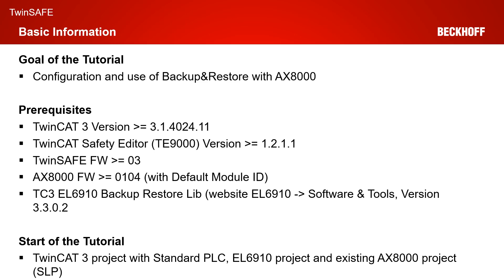As prerequisites, we need a TwinCAT 3 version greater or equal to 4024.11, a TE9000 version greater or equal to 1211. We need a TwinSafe firmware on the AX8000 greater or equal to 0.3. We need an AX8000 firmware greater or equal to 0.104 with the default module ID active. And for today's tutorial, we also need our TwinCAT 3 EL6910 backup restore library, which can be found on our website. At the EL6910, go to Software and Tools and you get the current version 3302.